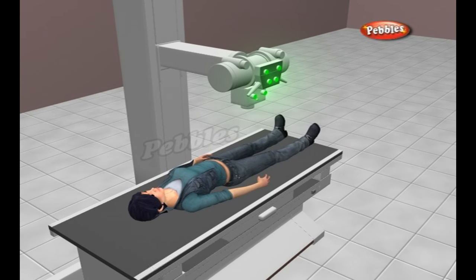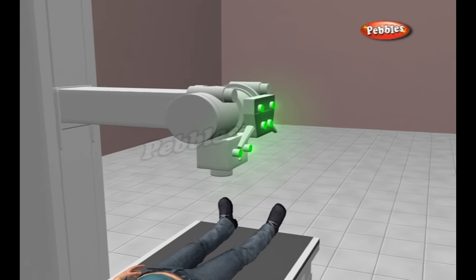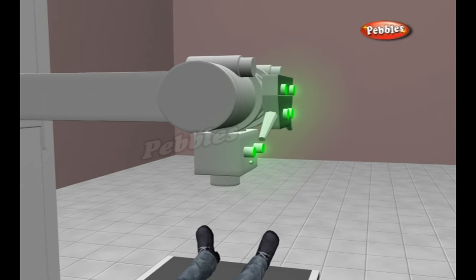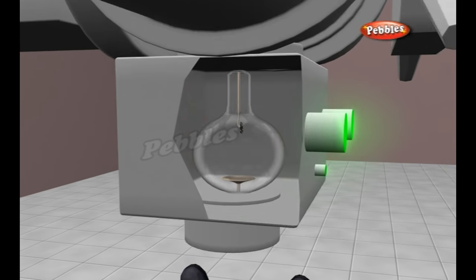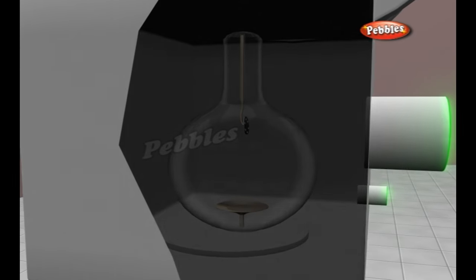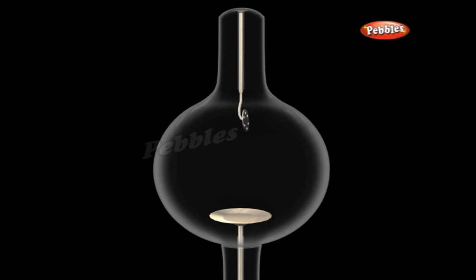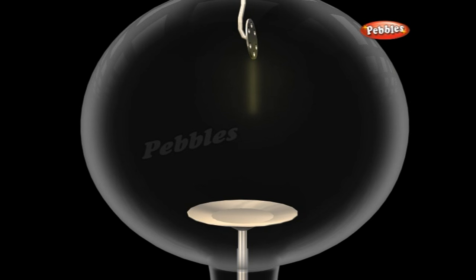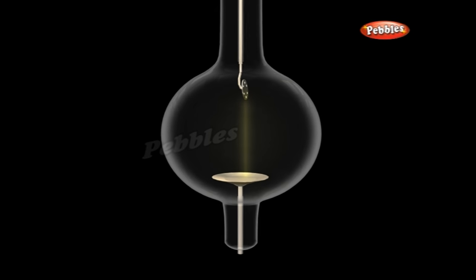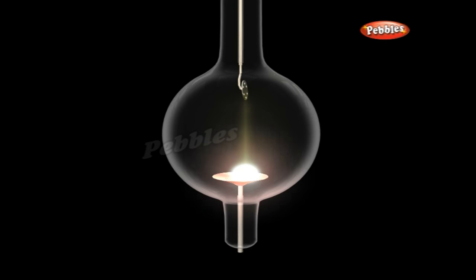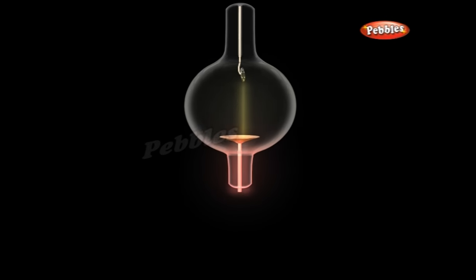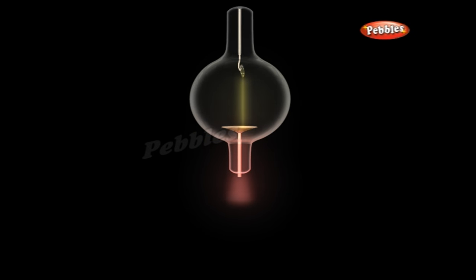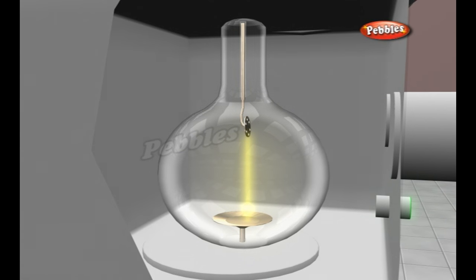The X-ray machine is composed of an X-ray tube that contains a pair of electrodes, or conductors, called a cathode and an anode. The cathode is a filament that releases energy with the introduction of an electrical current, much like that of a light bulb. The cathode energy is released in the form of electrons. The anode, located on the opposite end of the X-ray tube, is a disc made of tungsten, a material that attracts the electrons. When the electrons released from the cathode come in contact with the tungsten, they release energy in the form of photons.